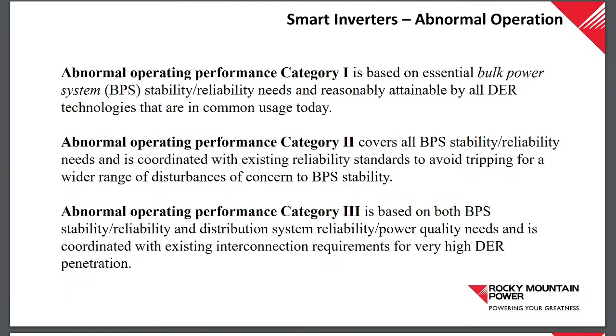What abnormal operations means is inverters now, if there's a system disturbance, like a fault on our system, lightning strikes it, or a bird runs into our line, that can momentarily dip the voltage. Right now, if the voltage dips below 0.9, 90% of normal, the inverters will trip offline. So if there's a system-wide disturbance, a lot of inverters could trip offline.